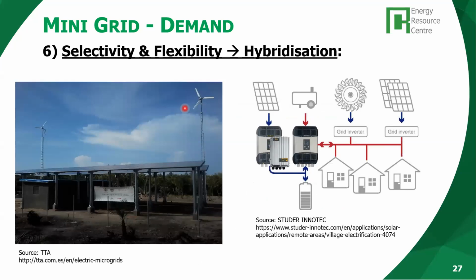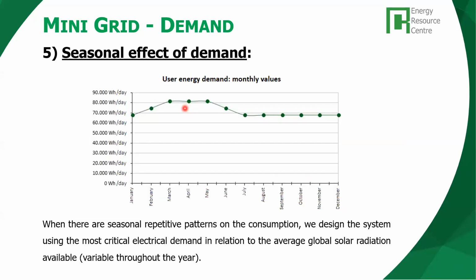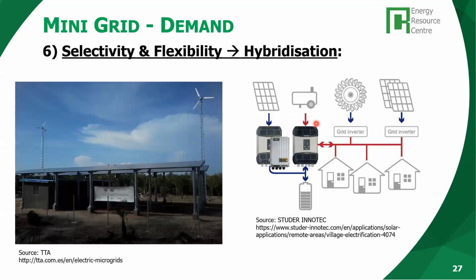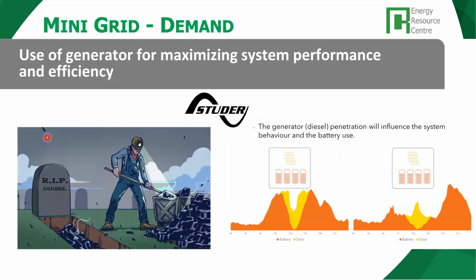For this kind of analysis, this is why we consider the aspects of selectivity or flexibility in the generation. Which kind of consumptions are we going to consider as priority? Which ones are going to be secondary? Can we consider a strategy to assign the primary consumption with priority from the solar system and the secondary consumption, not so much priority, from genset, for instance? This is an example, schematics from Studer, again, from Switzerland, where they can have, you see, different generations, solar generation, diesel genset, or hydro generation, for instance. A mini grid that I worked with, and the company TTA, you can see the solar system, but there's also generation with wind.